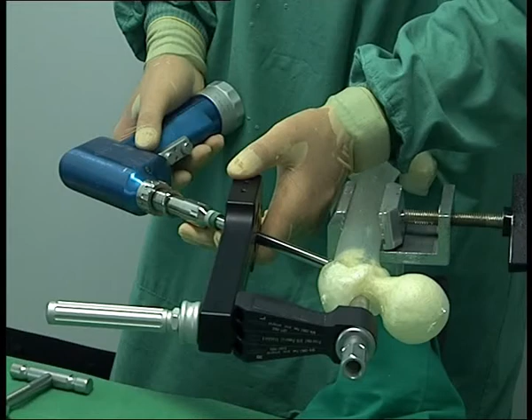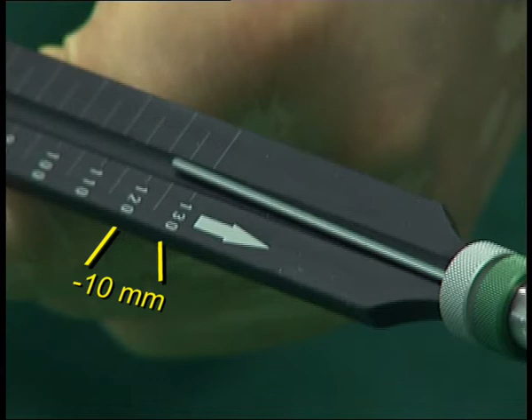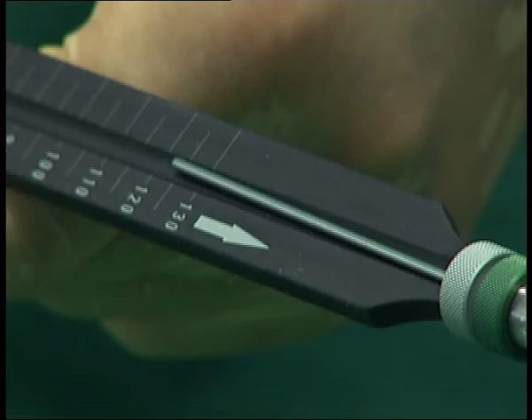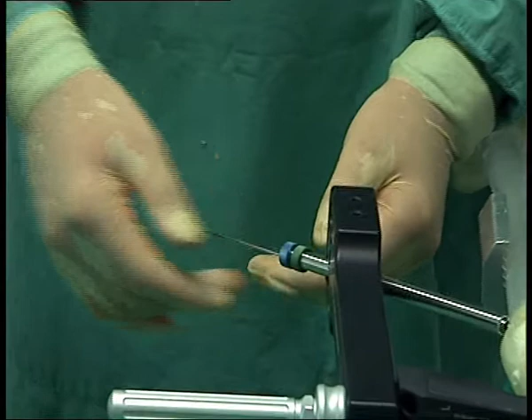Now lay the screw depth gauge with its grooves at the drill wire flush against the silver drill sleeve and read off the measured length according to the calibration. Determine the real length of the screw by subtracting 10 mm from the measured length. When this has been done, select the appropriate sliding screw. After this procedure, remove the silver drill sleeve and replace it with the blue drill sleeve.